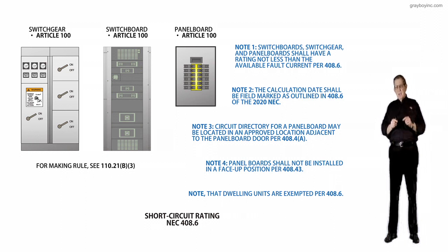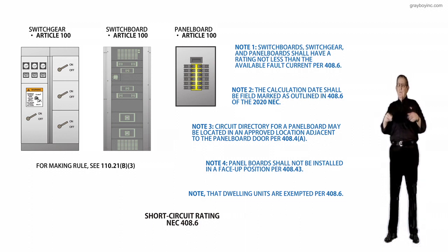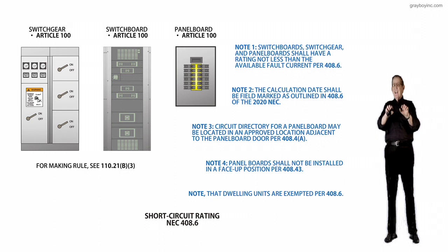Some of your cities still practice this because it was in their ordinance. So they wanted to point out, no, if you have a 10 kA breaker, then it would interrupt your 10 kA with these new modern type circuit breakers available to us today. So that was kind of the impact of Note 1 in the 2017, further stated in the 2020 NEC.